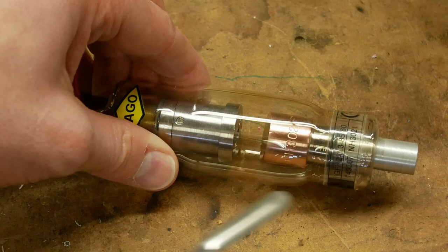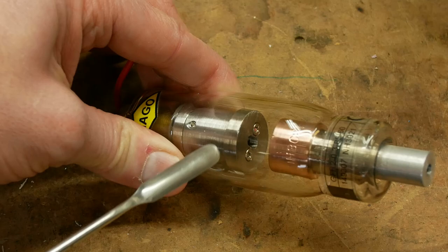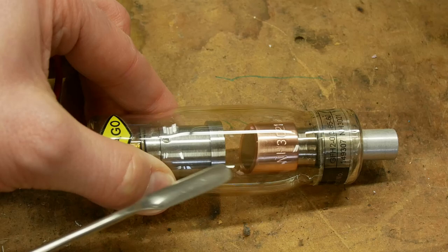So the thing to know is that inside that little cup where the filament is, there's some carefully controlled geometry to focus the electron beam down to a very tight spot. The smaller the spot size, the better the resolution.